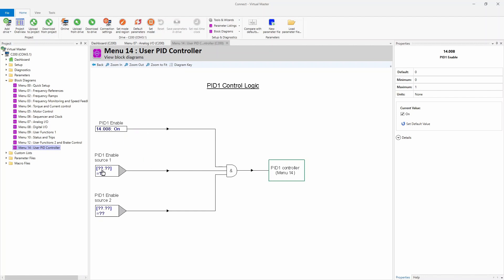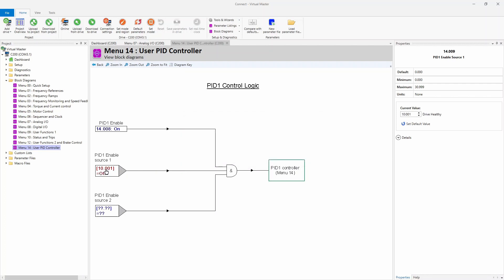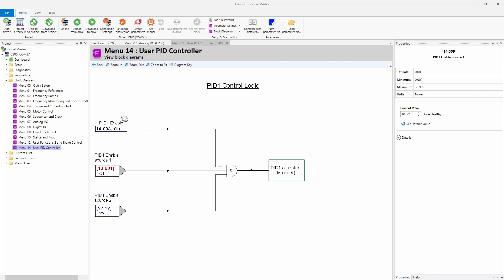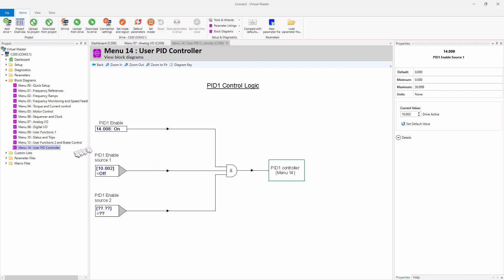If you map this somewhere, for example, 10.01, which is drive healthy, then not only would the drive need to be healthy, but this would also have to be enabled in order for the PID to run. Most of the time I don't use drive healthy. If I was to use something, I'd probably use drive active, which is 10.02. As you can see, when I put my mouse over the parameter, that way, when you remove the run command, it automatically disables the PID.